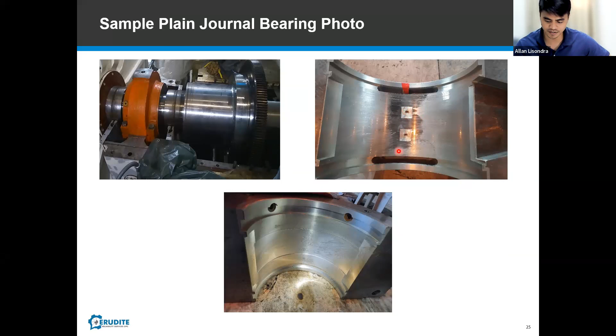Now we will discuss the proximity probe. Since we are using journal bearings, the applicable probe we have to use here is the proximity or non-contact eddy current probe. It measures the displacement, or the distance, between the tip of the probe and the shaft, so it measures the movement of the shaft within the bearing. Since we're interested in the movement of the shaft relative to the bearing, the proximity probe is applicable. The measurement is in mils or microns peak to peak. The sensitivity of this probe is 200 millivolts per mil, or 8 millivolts per micron.